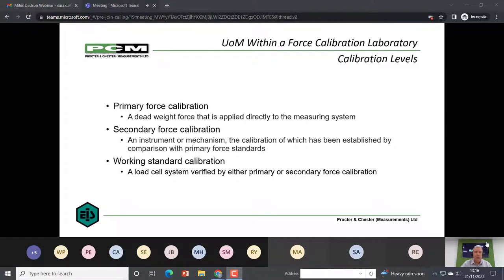There are several levels of calibration. The first one, or the top level, is a primary force calibration, where you actually use dead weights. The kind of facilities that will operate these are National Physical Laboratory, which has several, and their compatriots over in Europe, and also in America too. Some other manufacturers may use these. We'll come on to the pros and cons of that very shortly.